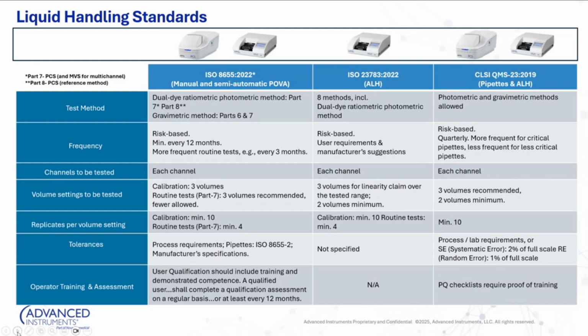So again, they're really providing the lab some autonomy to think about how your pipettes are used and what's really important. They follow the same thought process as ISO as far as the number of channels to be tested, every one of them. And they also follow similar thoughts with regards to the volume testing. 3 volumes are recommended, a minimum of 2 volumes for calibration. The replicates, minimum of 10, and then tolerances, very similar to ISO. However, they have some very specific permissible errors when it comes to systematic error and random error. So plus or minus 2% for systematic error or accuracy, as some of you might refer to that, and then 1% of full scale for random error or imprecision. So they have some distinct suggestions if you decide to not implement a process or lab requirement. And then with regards to operator training and assessment, performance qualification checklists require proof of training. And that's really as much as they say.